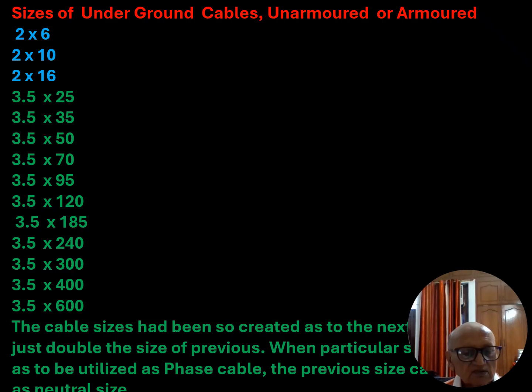Over 600 we don't have 3.5. It is always single core cable. These cable sizes have been created in a manner that the size just below is half in square millimeter area of cable conductor.